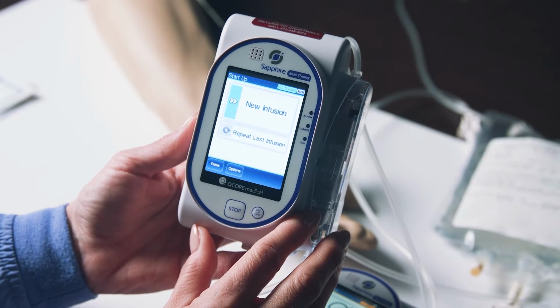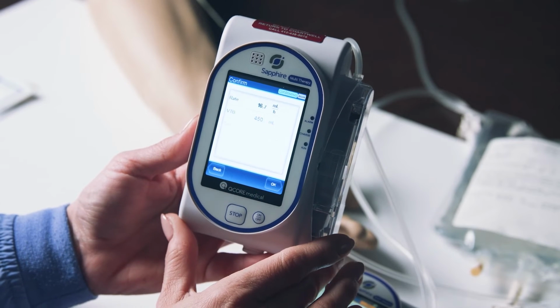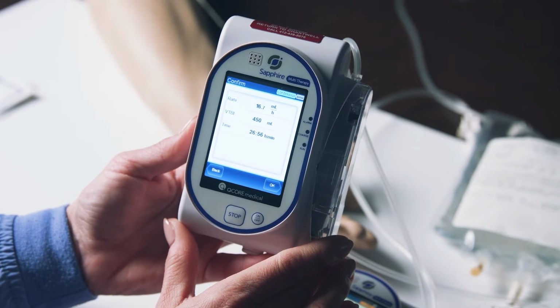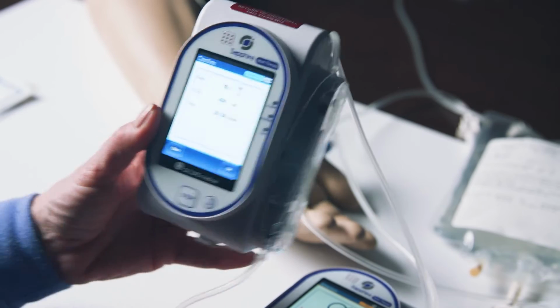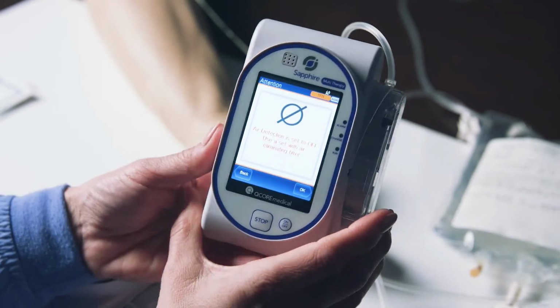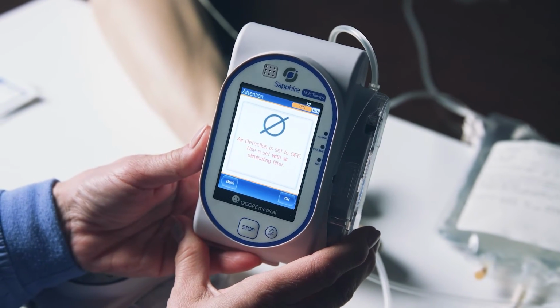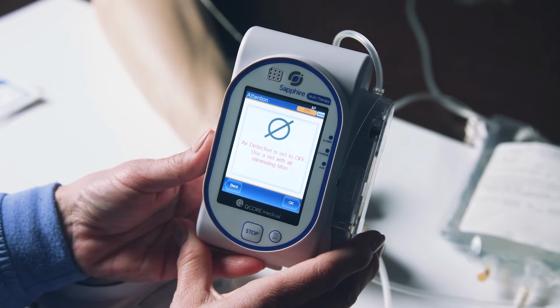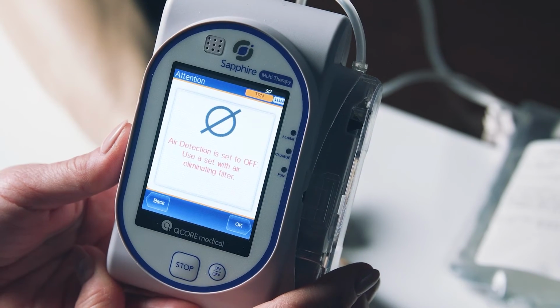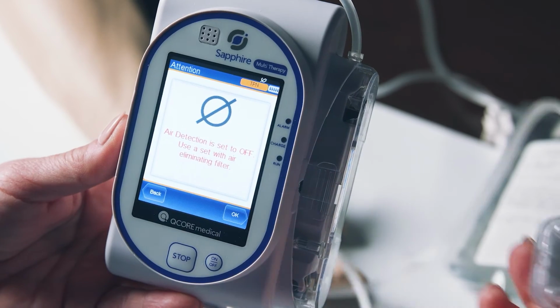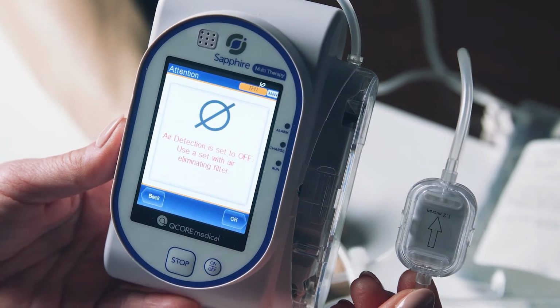To start your medication dose, press Repeat Last Infusion. When you press Repeat Last Infusion, your pump will either display the pump's settings or display the No symbol and read, Air detection is set to off. If your screen displays the No symbol and reads, Air detection is set to off, use a Set with Air Eliminating filter.